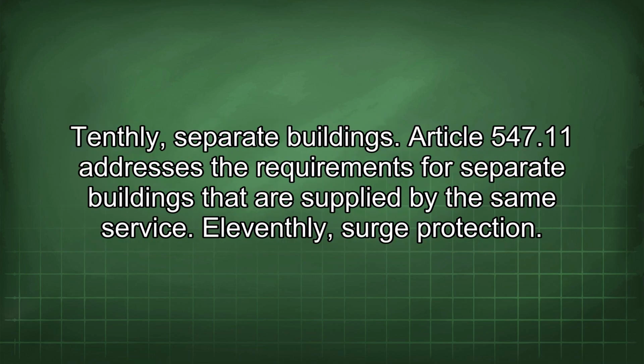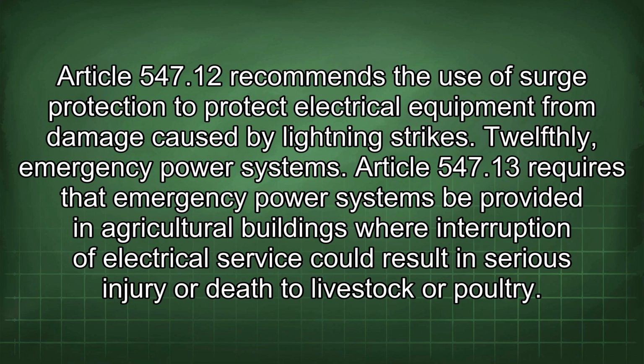Tenthly, separate buildings. Article 547.11 addresses the requirements for separate buildings that are supplied by the same service. 11thly, surge protection. Article 547.12 recommends the use of surge protection to protect electrical equipment from damage caused by lightning strikes. 12thly, emergency power systems. Article 547.13 requires that emergency power systems be provided in agricultural buildings where interruption of electrical service could result in serious injury or death to livestock or poultry.